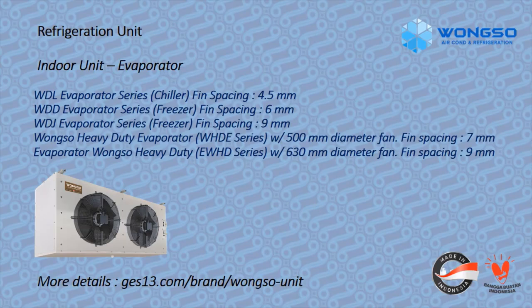Beranjak ke evaporator unit, ada 5 jenis evaporator, yaitu yang pertama, WDL series, digunakan untuk aplikasi medium temperature atau chiller. Didesain khusus untuk SC2 condition, yaitu suhu evaporator -8 Celcius dan suhu ruangan 0 Celcius, menggunakan fin spacing 4,5 mm. Memiliki kapasitas mulai dari 2 sampai dengan 116 kW. Menggunakan axial fan mulai dari diameter 350 mm sampai 710 mm dan dilengkapi dengan diffuser.